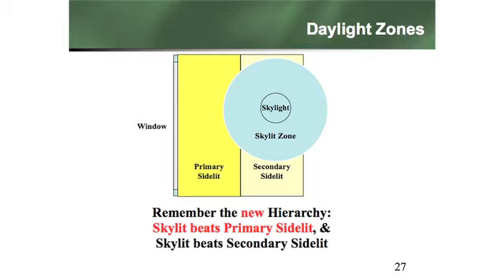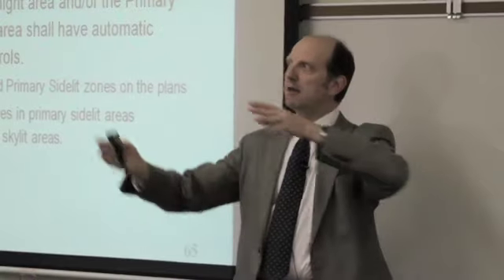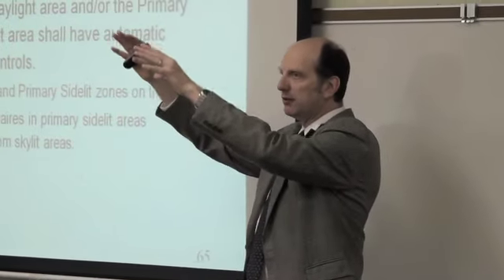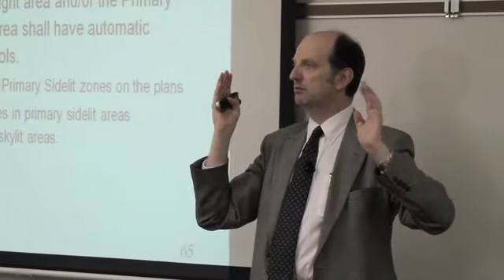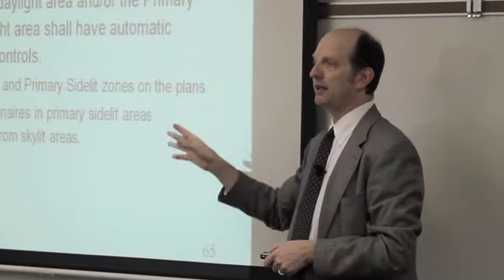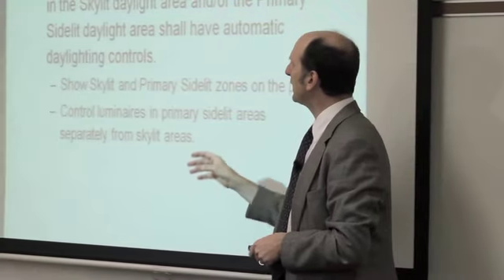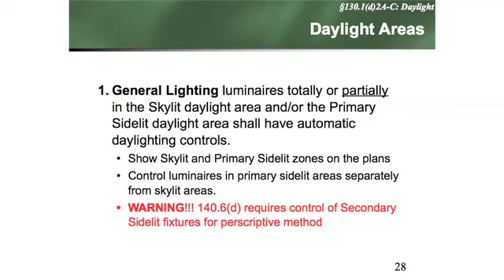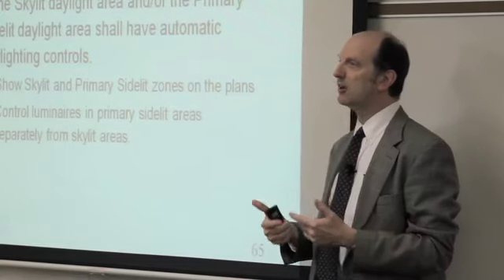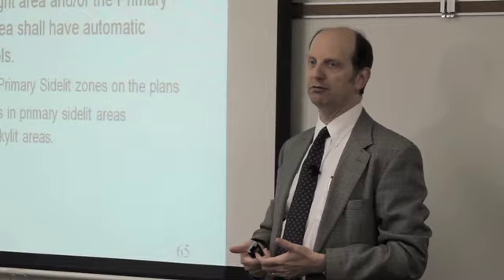So now here's the rule. It used to be that they'd say, okay, well, if you had a daylighting zone, you needed to be able to take the lights in the daylit zone and reduce them without touching the rest of the room. Okay? They got rid of that whole idea. The reason is because they've now mandated in the primary side lit and any skylit zone that you have to have automatic daylighting controls. So daylighting controls are going to be all over the place in California.